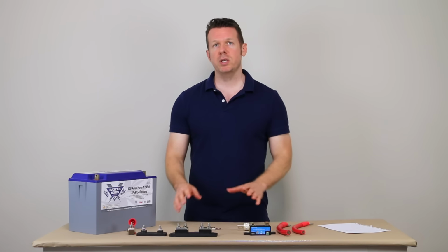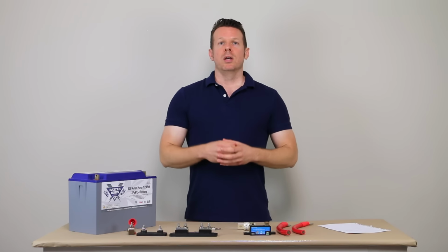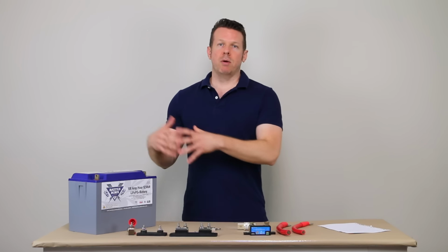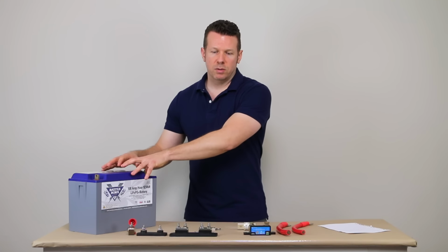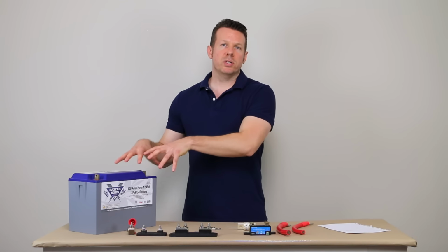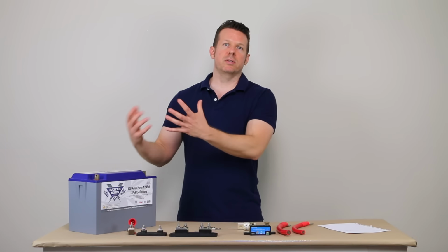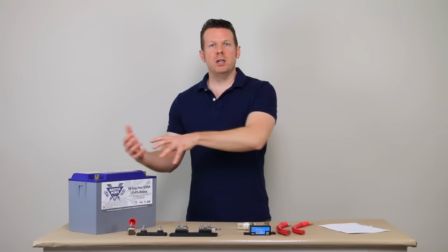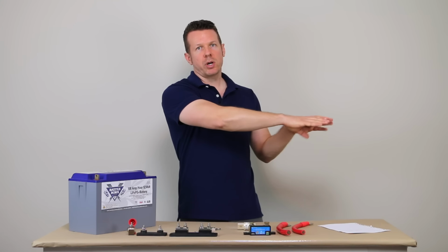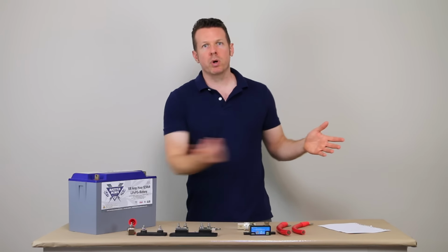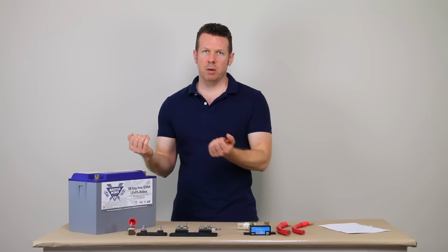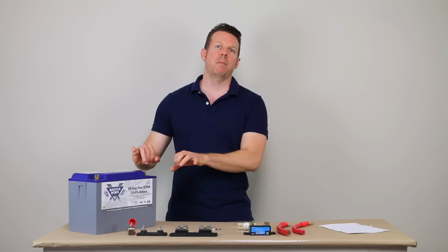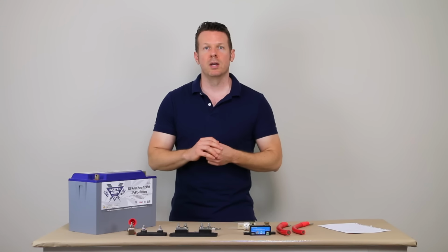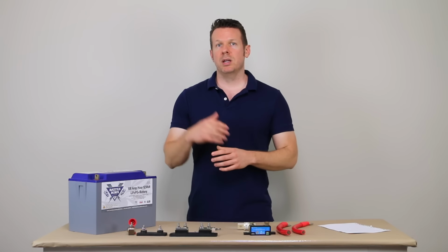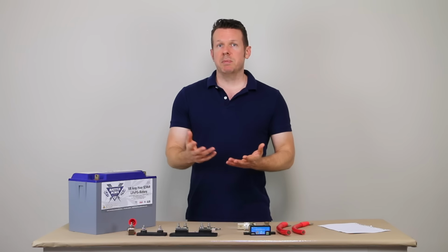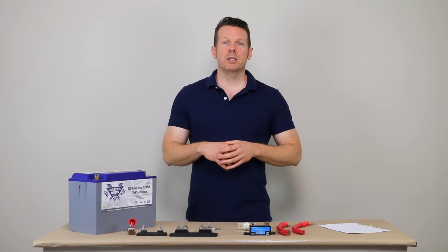Now, the difference between these is the interrupt rating, and that's why they're approved as a main battery fuse. The batteries can put out quite a lot of current, thousands of amps, right? And we need to be able to stop that power. If there's a short circuit out in the system and the batteries want to dump out all of their power, we need to be able to blow that line and stop that power from getting out of the battery bank. And that's where interrupt current comes in. And so these three fuse types have a higher interrupt current.